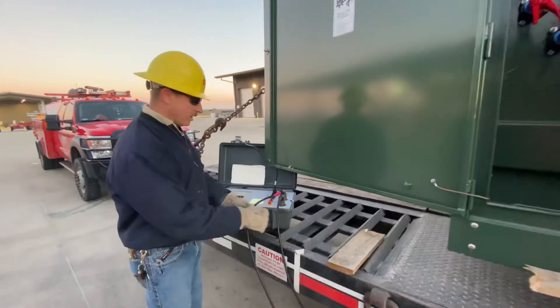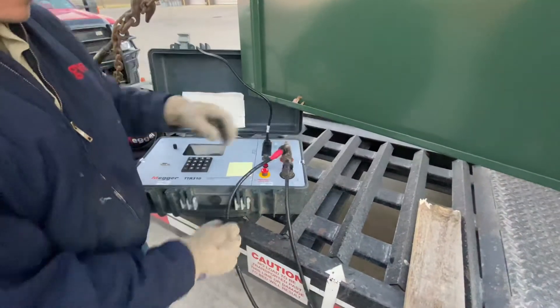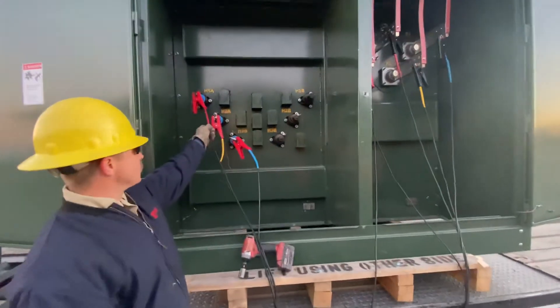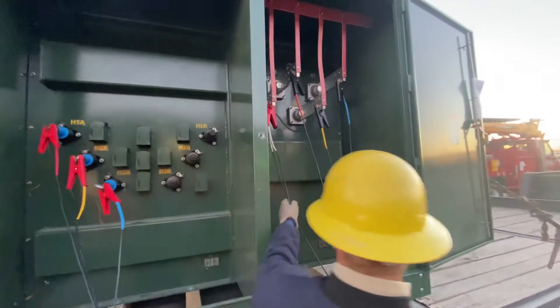The TTR machine has two leads on it, plugged in right here for your H and X. Each lead has four cables attached to it. The primary side is going to have an H1, H2, H3, and an H0 on your neutral version.